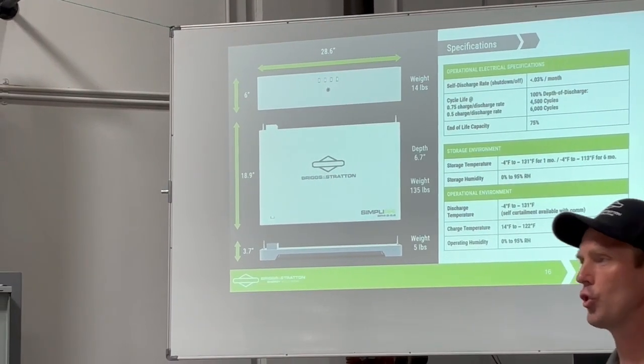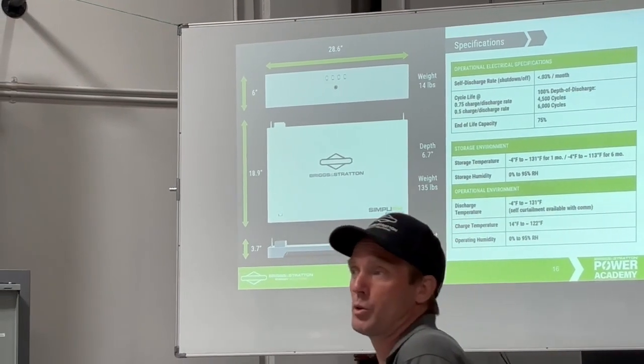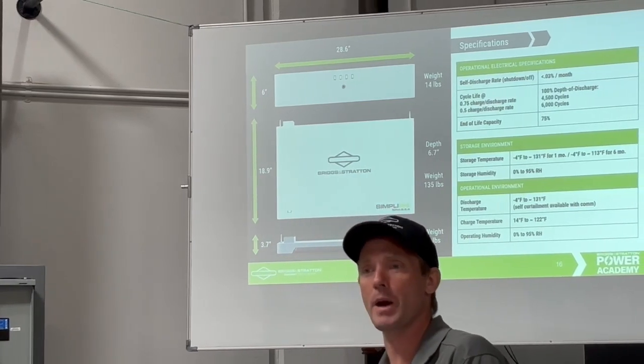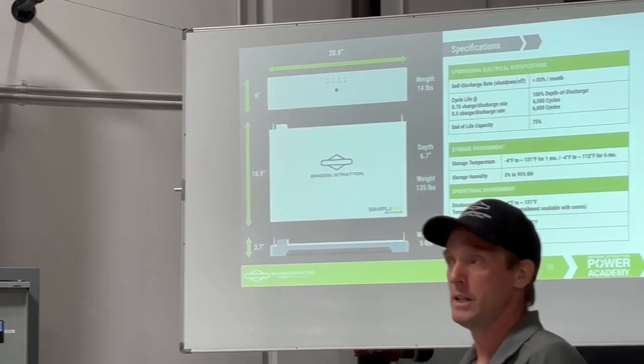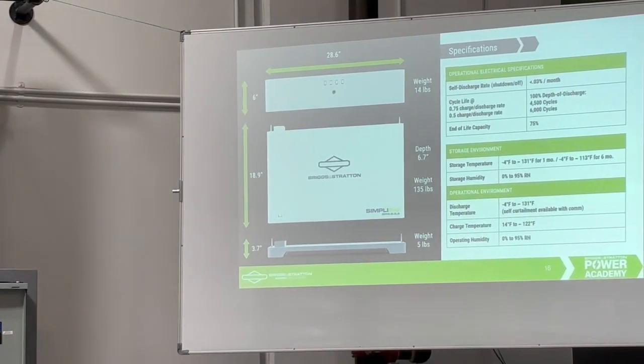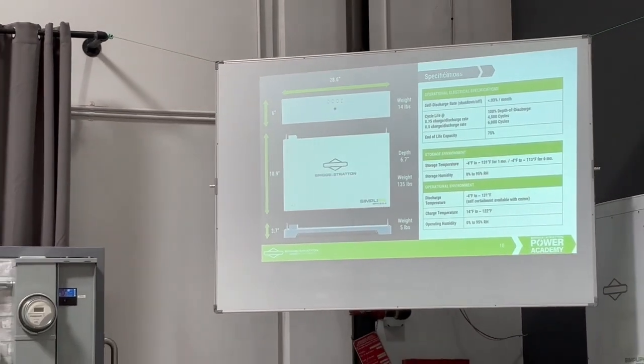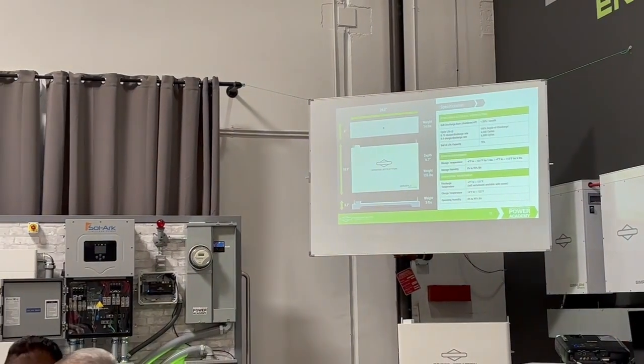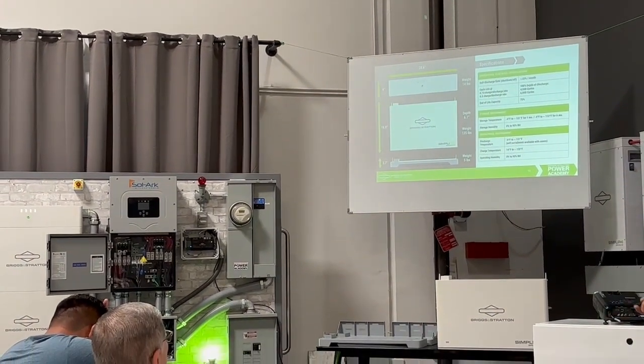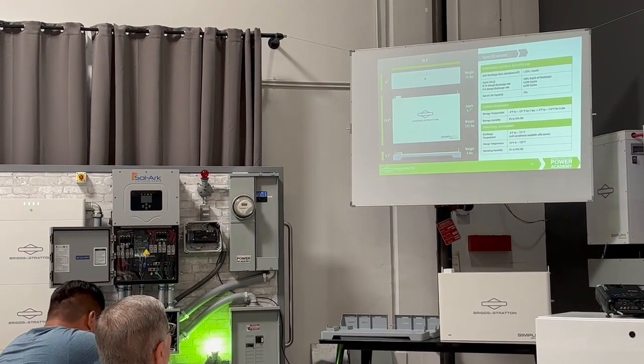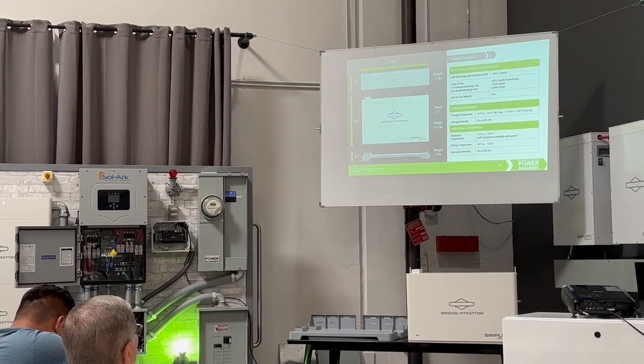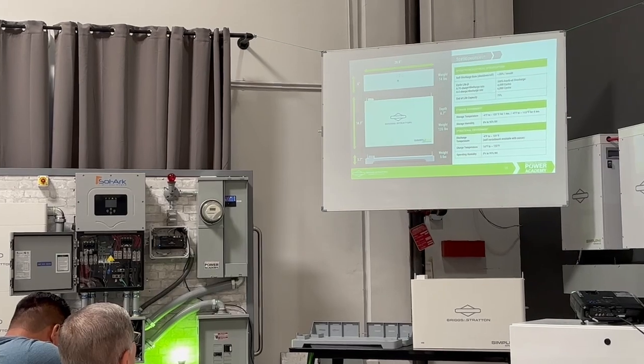Cold temperature, early morning, it's cold but the sun is out. Your batteries start charging earlier with our battery versus some of the competition that doesn't start charging until 32 degrees. I believe the Powerwall might not charge until 32, and there are other batteries in the market that don't start charging until then either. So if you're doing an altitude installation in cold weather as a consideration, these batteries will get started charging a bit earlier. Also, we've got a pretty fast charge and discharge rate.